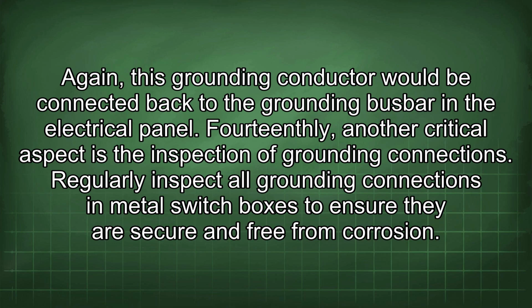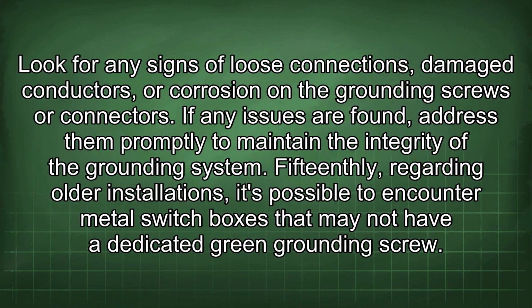14thly, another critical aspect is the inspection of grounding connections. Regularly inspect all grounding connections in metal switch boxes to ensure they are secure and free from corrosion. Look for any signs of loose connections, damaged conductors, or corrosion on the grounding screws or connectors. If any issues are found, address them promptly to maintain the integrity of the grounding system.